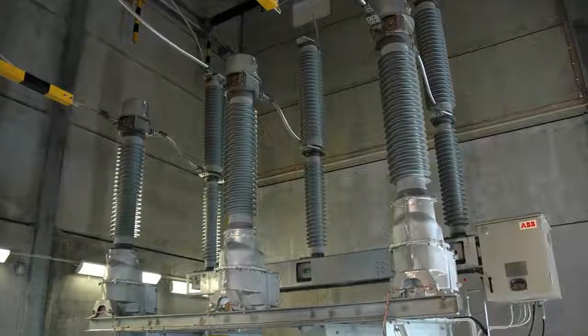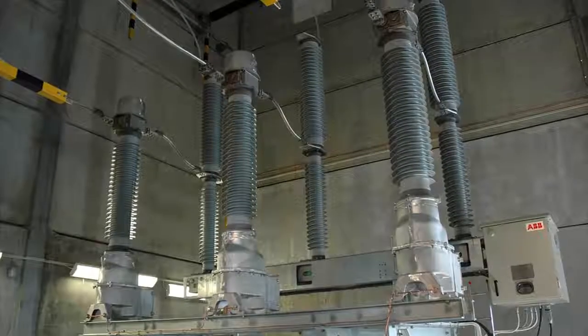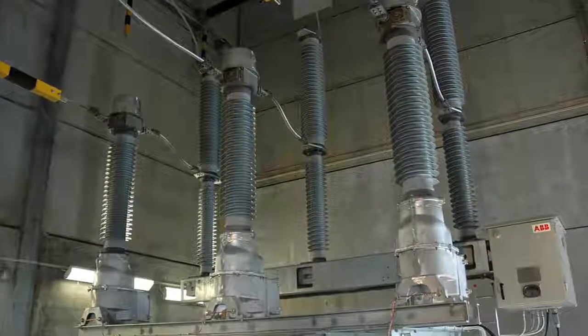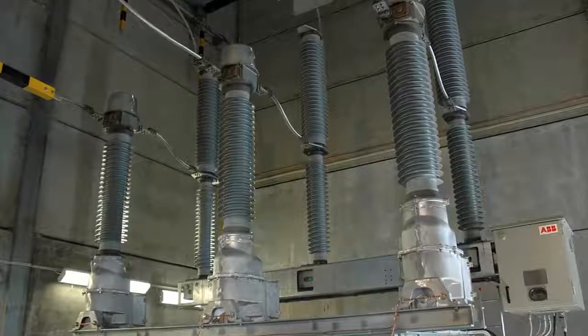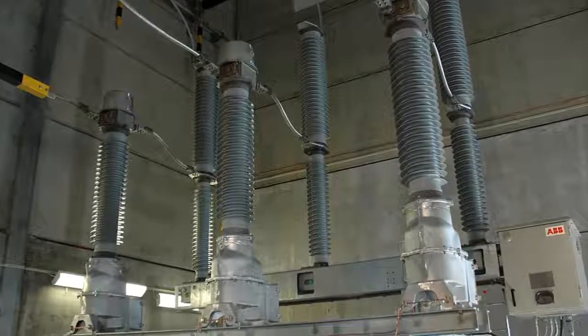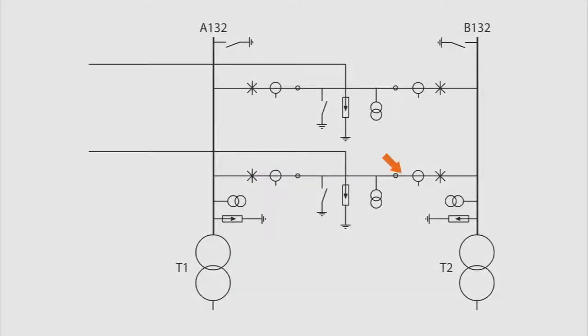You will now see how you can perform maintenance on a disconnecting circuit breaker without taking the 132 kilovolt substation and the lines out of service. The substation has a ring bus setup containing 2 lines, 2 transformers, 2 bus bars, and 4 disconnecting circuit breakers. Each transformer is connected to 1 bus bar.